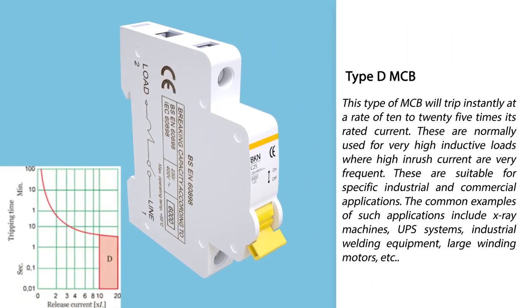Type D miniature circuit breaker will trip instantly at a rate of ten to twenty-five times its rated current. These are normally used for very high inductive loads where high inrush currents are very frequent. These are suitable for specific industrial and commercial applications, with common examples including X-ray machines, UPS systems, industrial welding equipment, large winding motors, etc.